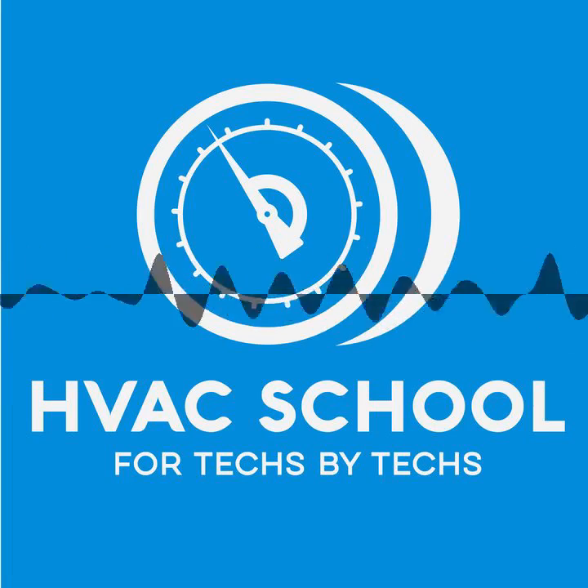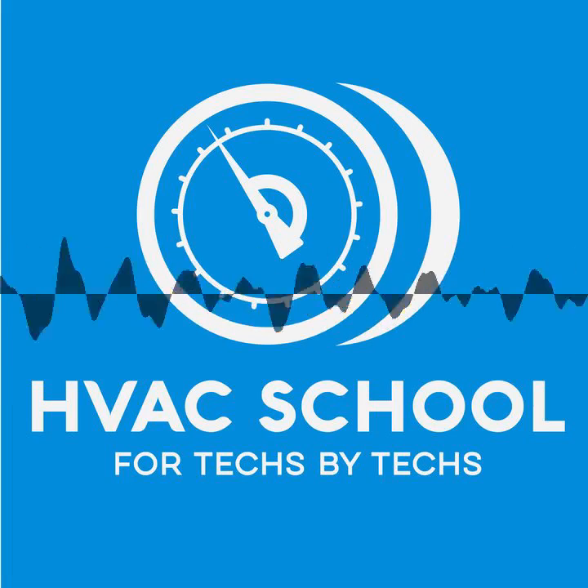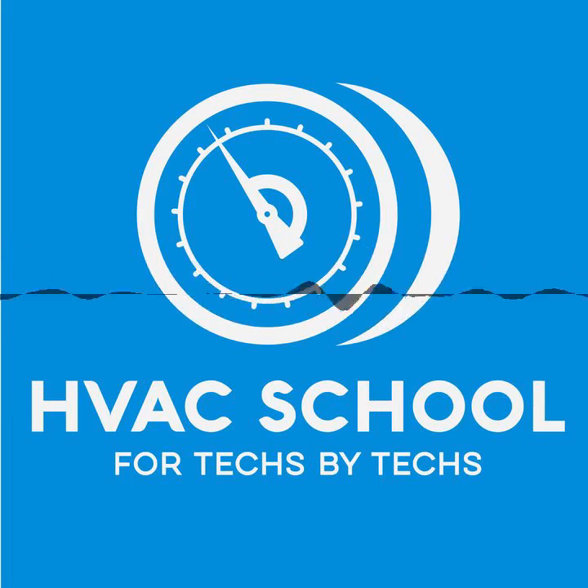And especially when it comes, if I can just jump in again, to superheat adjustment. Remember, people, each valve model has a different rate adjustment. We have air conditioning valves that are 1 degree of superheat change per full turn. We have some that are 4 degrees of superheat change per full turn. So you're either going to dial it down or out of whack so fast you're not going to know what happened, or you're going to be sitting around all day waiting for something to happen. Okay? So again, this information is not something you have to travel 500 miles and attend a course to learn. It's right on the side of the box, or it's on the product data sheet, and with our smartphones, we can get this stuff.